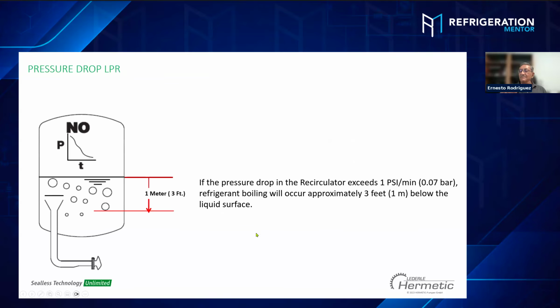Okay, let's go back to the pressure. We need to keep this pressure drop small. When we drop the pressure over 1 psi or 0.07 bar, the refrigerant starts boiling inside the vessel, meaning those bubbles will go back to the pump suction.